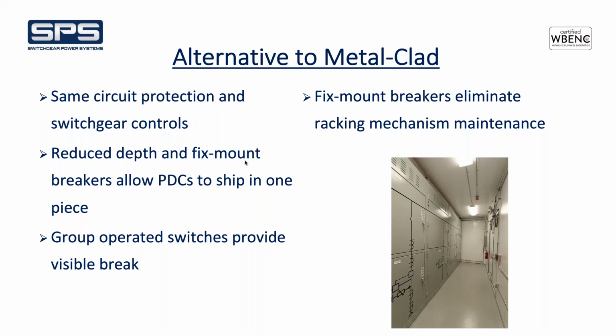As I mentioned before, the visible break that you would normally get from the draw breaker is provided via group operated switches. And then we believe fixed mounted circuit breakers provide an advantage of not having to do maintenance on the racking mechanism. Anybody who has been around or experienced metal clad switchgear understands that the circuit breaker racking mechanism is a very mechanically complex device, requires maintenance, and can break down. It's one of the most common failure points on a switchgear unit. So having a fixed mounted breaker eliminates those potential points of failure.